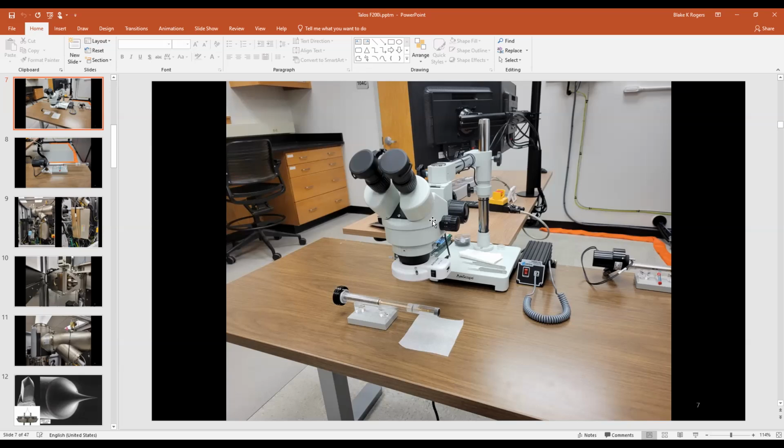But once you have your sample in, it takes a minute, no? Yeah, we'll put your sample in. We let it sit for 2 minutes under vacuum before we fully insert it into the column. And then from that point on, it takes a few minutes, we get the Z height right. Once we get the Z height set, we set it to what's called eucentric height. And then from that point on, a lot of these pictures were done really quickly, because Jesus would bring in 6 samples and we would go through 6 samples in an hour's time and get 10 or 12 pictures of each one.